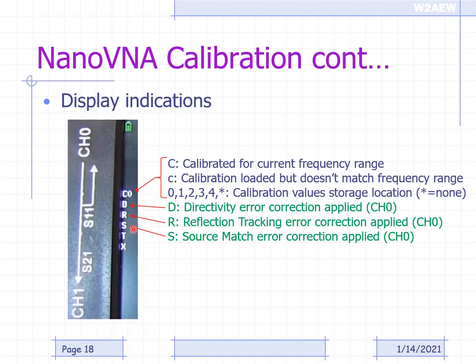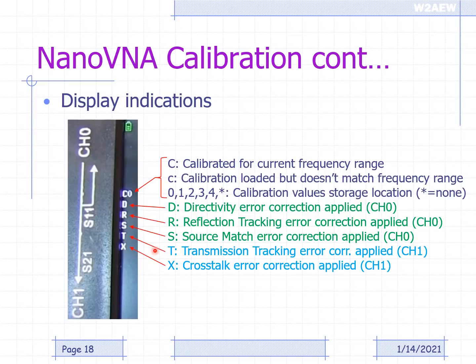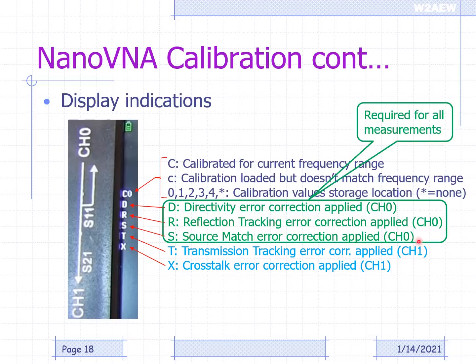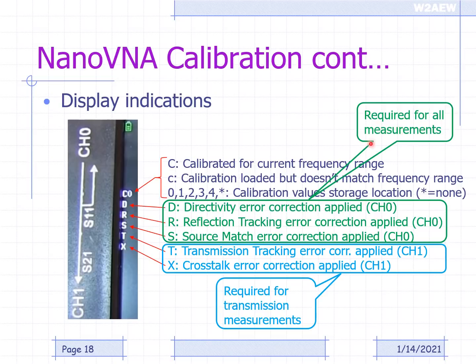The D, R, and S are for all of the channel 0 calibrations, indicating that those corrections have been applied. And then the T and the X stand for the transmission and crosstalk error corrections being applied for channel 1. These first 3 are needed for all the measurements you're going to make. The second 2 are only needed if you're making transmission measurements. So if you're not making transmission measurements, you can ignore that portion of the calibration process.